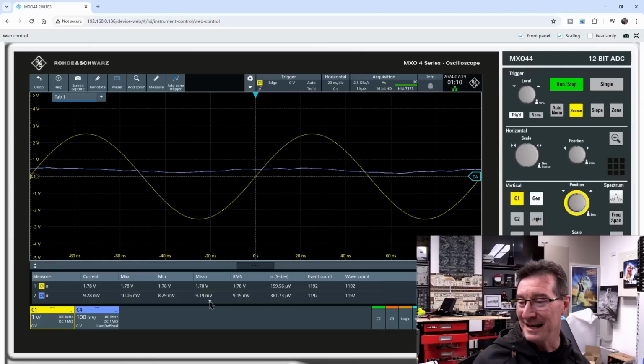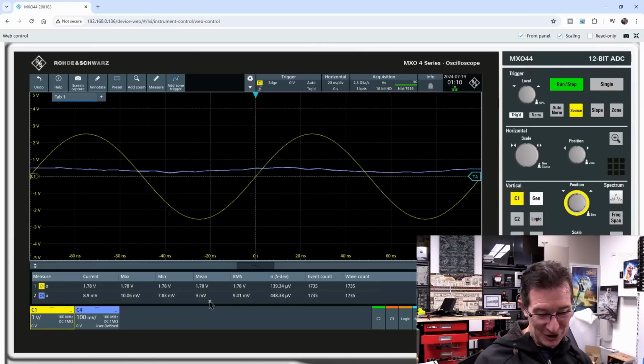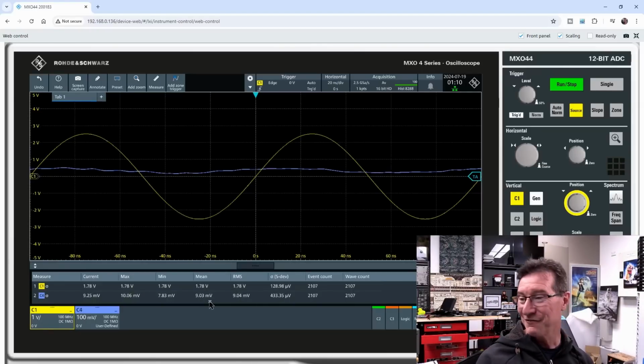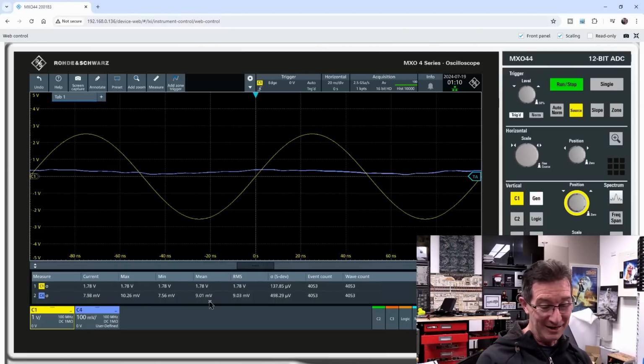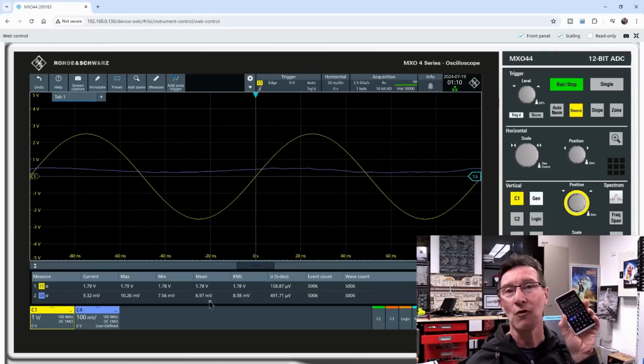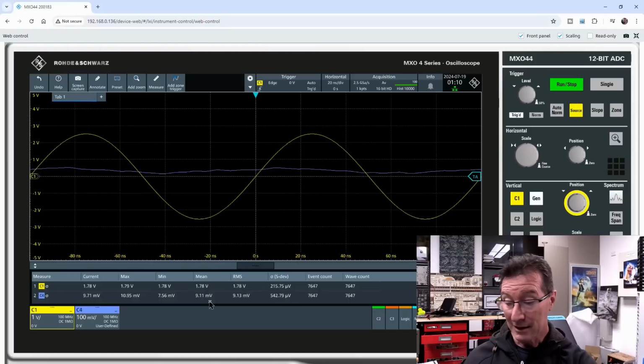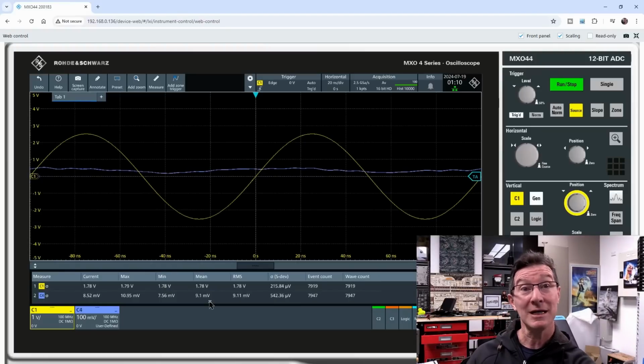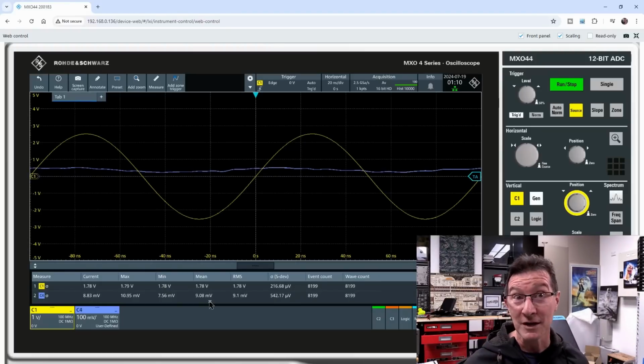So a mean here of 9.2 millivolts, divided by 1.78 volts. And then we get our log of that, and then we multiply that times 20, and that gives us minus 45 dB. And our 10 megahertz spec is minus 30 dB. So it's absolutely nailing that, no problems.